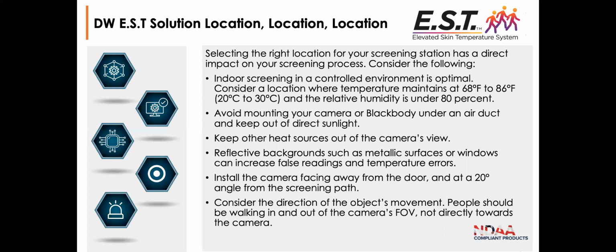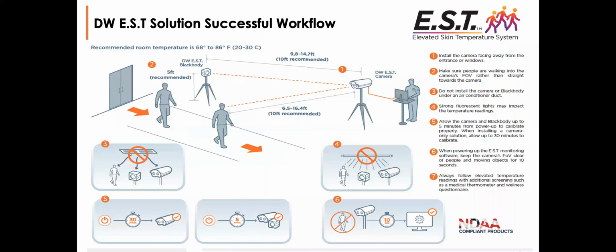For location, you want to keep other heat sources out of the camera's view. Avoid mounting the camera and black body under air ducts, as we've talked about, near reflective backgrounds and windows, and so forth. Install this facing away from the door at a 20-degree angle from the screening path, and have people go through one at a time. This is the recommendation for how to set this up.